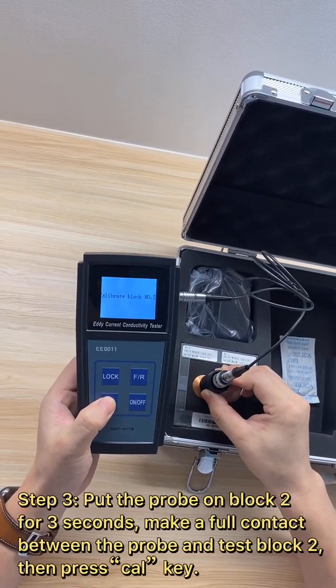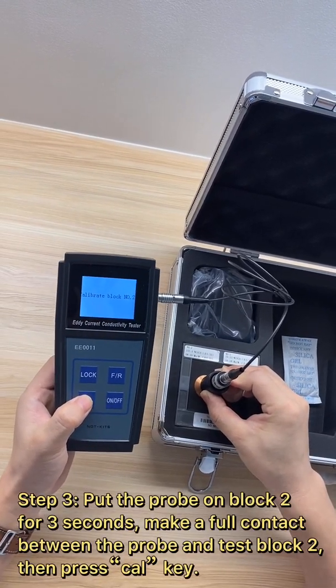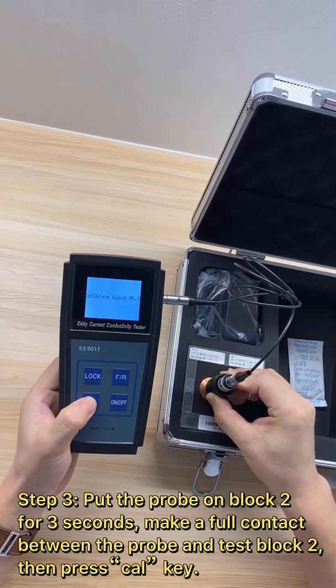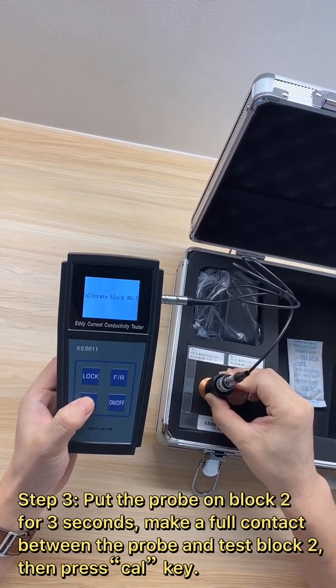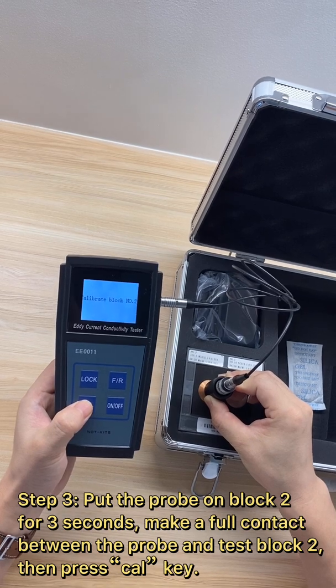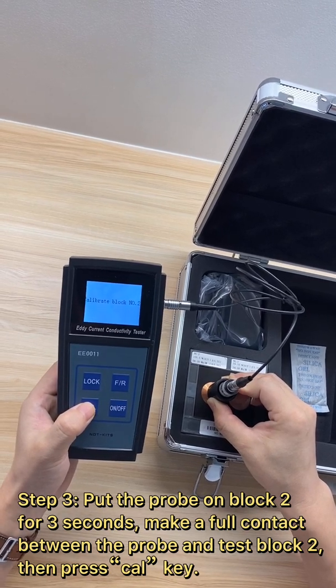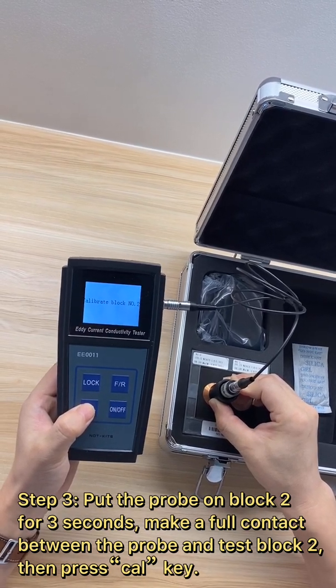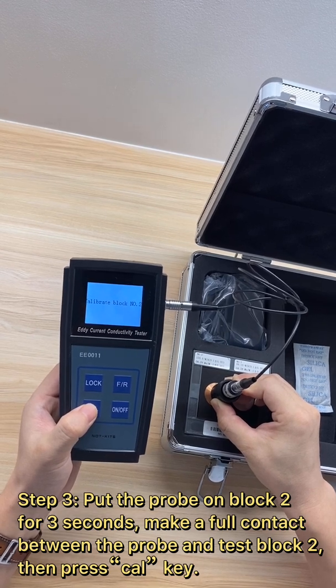Then put the probe on test block 2, like before. Make full contact between the probe and test block 2 for 3 seconds, then press the calibration key to complete the calibration process.